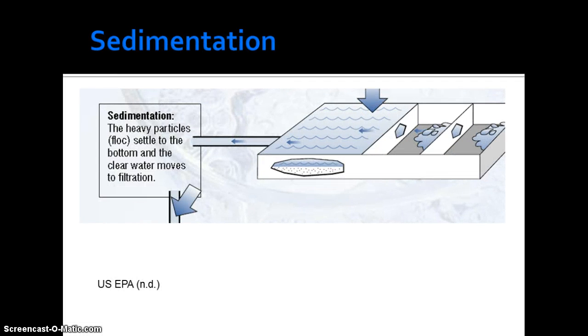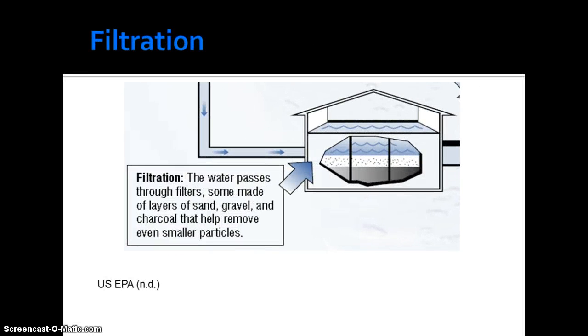In the sedimentation step, the floc — that is, the heavy particles — settle to the bottom and can be collected through a drain in the sedimentation basin floor. In some cases, lighter materials like oils and greases may be skimmed from the surface, depending on the quality and constituents of the incoming water. Clear water then moves to filtration, where it passes through filters made of a variety of materials tailored to the quality of the water being treated. Filter layers may be made of sand, gravel, or charcoal to remove different target chemicals and biological organisms.